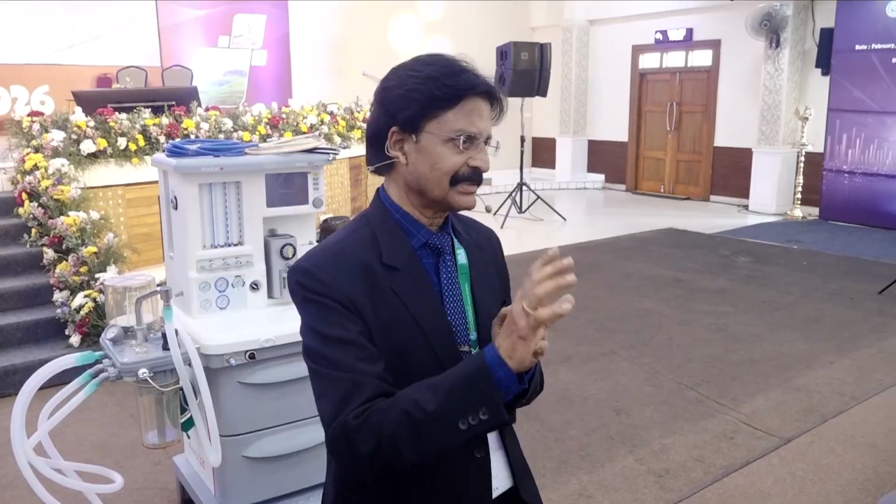Just imagine that there are no pressure regulators and you are using the cylinder, and you have started with 3-liter oxygen with a 2000 psig pressure of the newly delivered oxygen cylinder. After say 5-10 minutes, the cylinder pressure will drop down to 1900 pounds per square inch. What happens to your flow? Flow also will reduce.